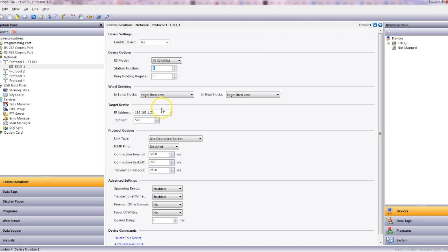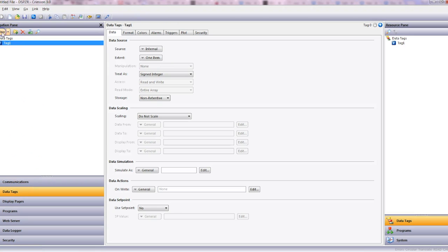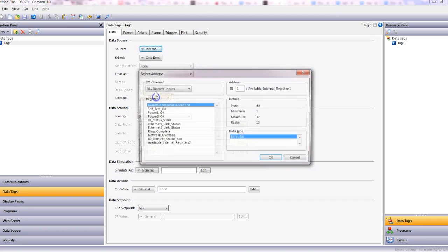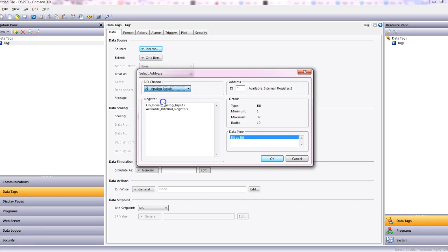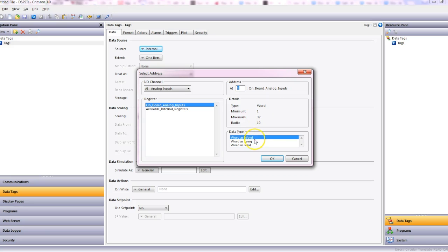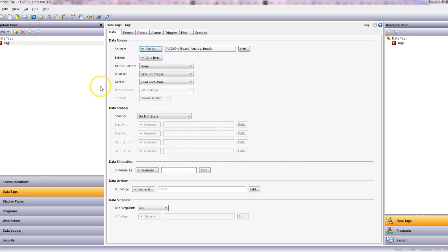Well now let's set up tags. So let's go to data tags and select new tag. Data source will be the new module we've just created, so E3 IO, and we're going to select the analog inputs. We have the onboard which is the physical and then the internal which is the internal registers. So analog input 1, onboard IO, analog input. The type word is 16-bit, long is 32-bit integer, and then real is 32-bit floating point. So we'll stick with the word and click OK.